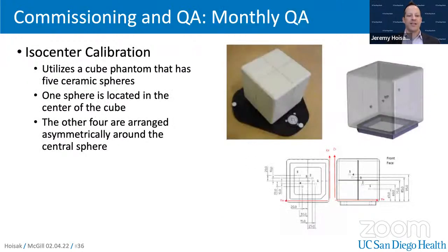Monthly QA utilizes a phantom that typically has a hidden target within it. So in this one, we have a cube phantom, which is compatible with surface imaging. And then we have spheres within. One sphere is located at the center, and the other four are located asymmetrically around it.